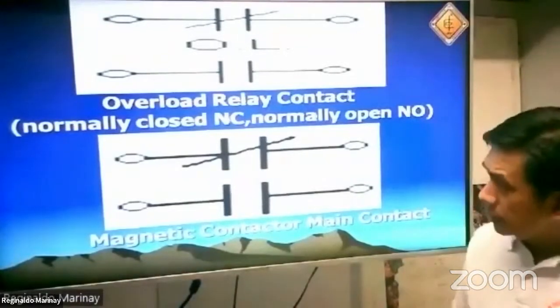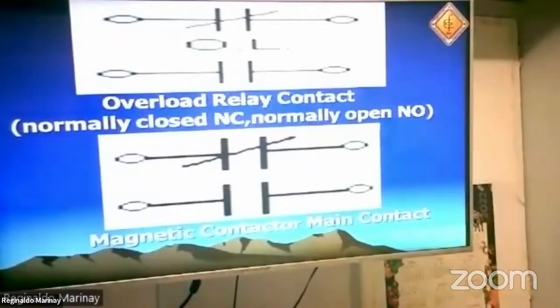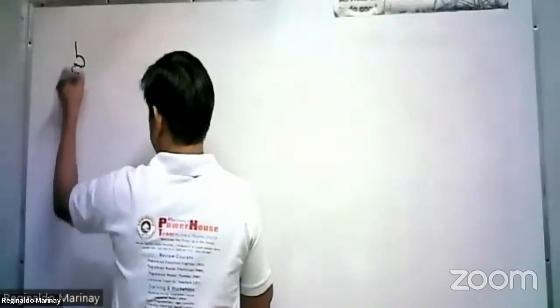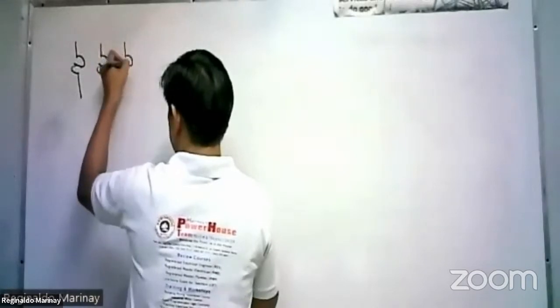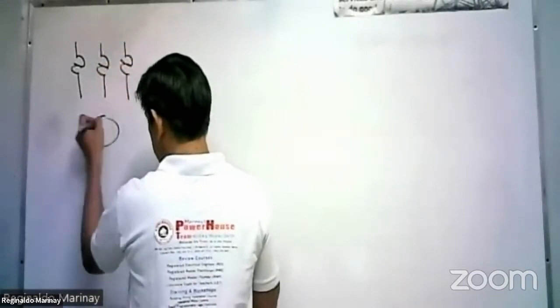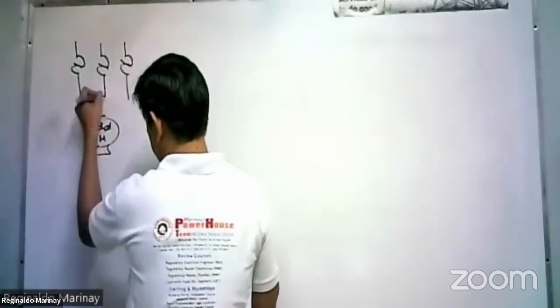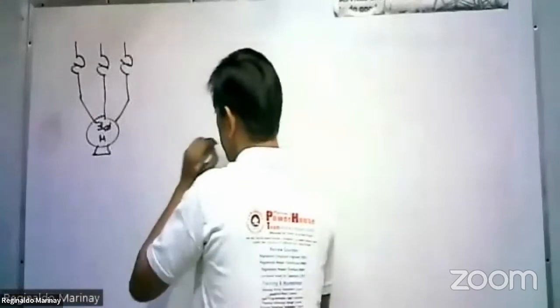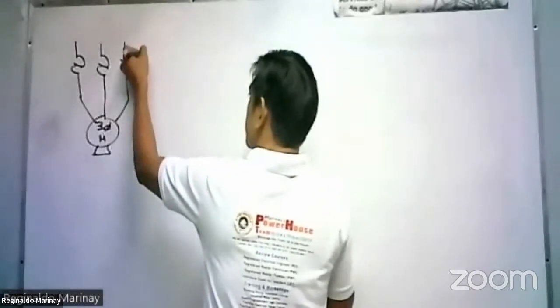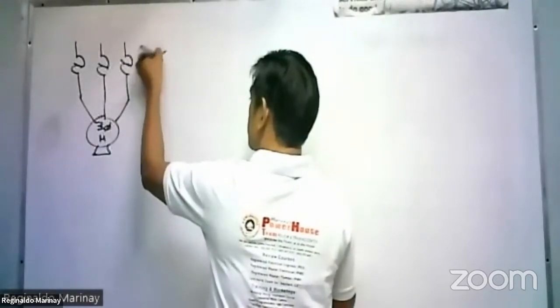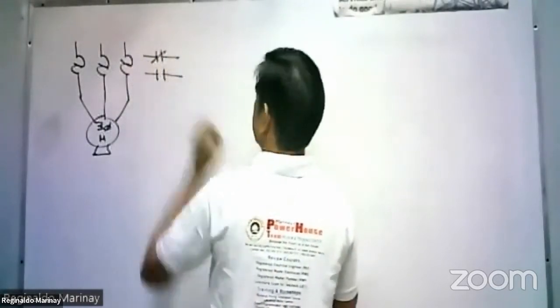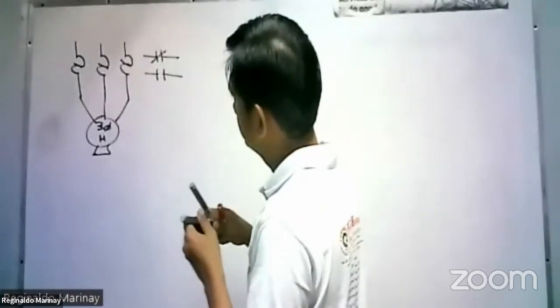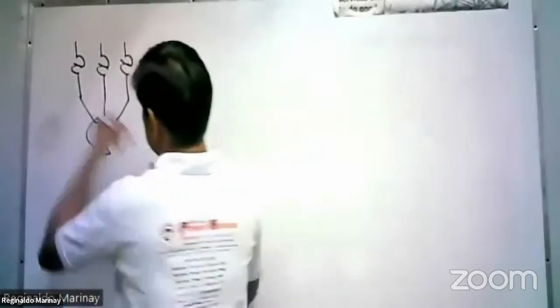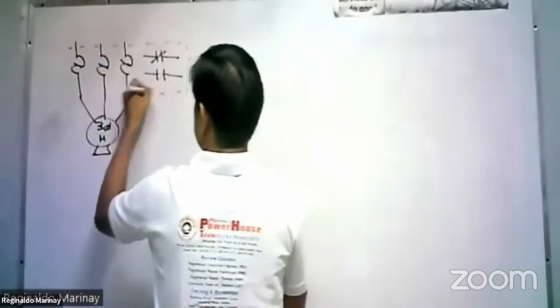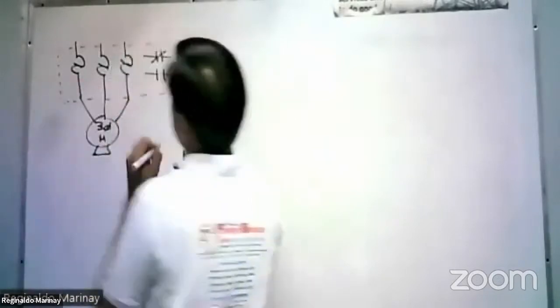If you will take a look at the overload relay, let's say a three-phase overload relay. Let's say this is the heater element of the overload relay. That is being connected to the three-phase motor. Let's say this is the three-phase motor. And then you will see a contact here. This is only one device.